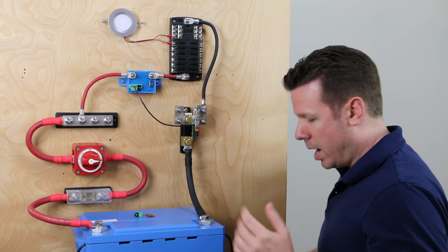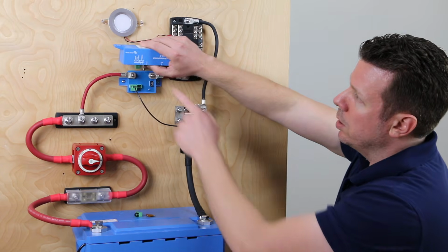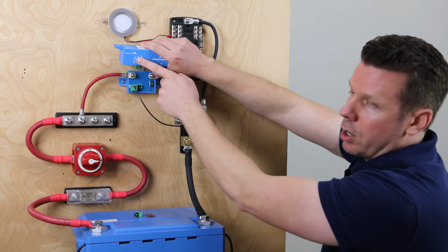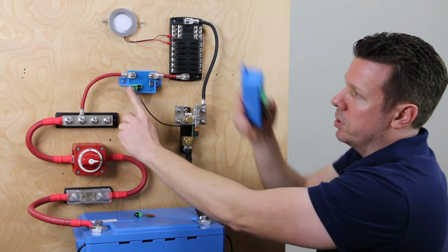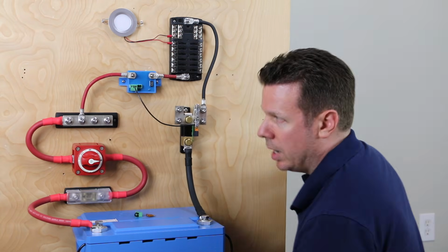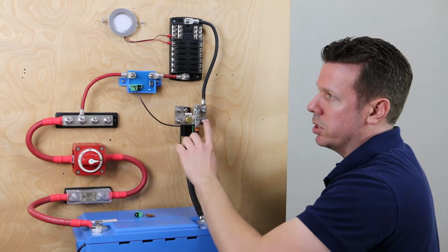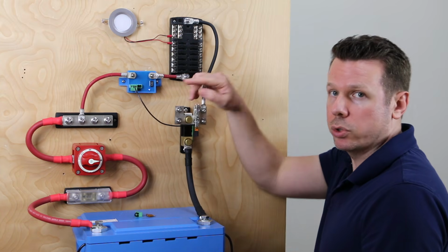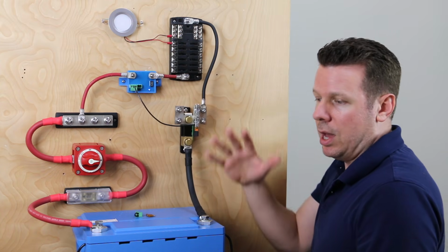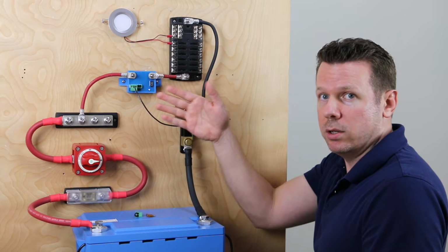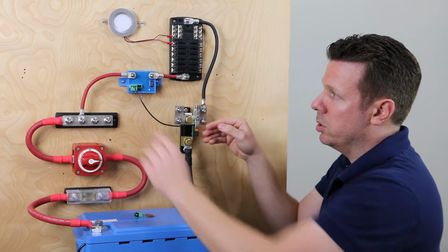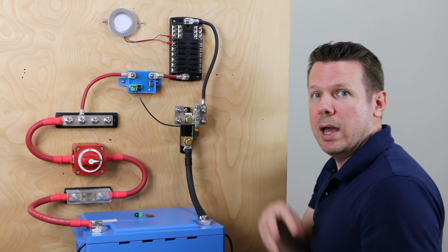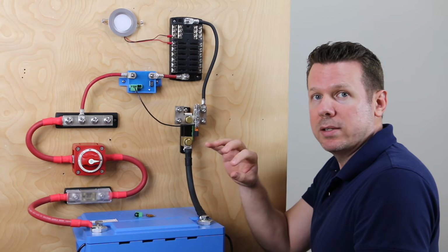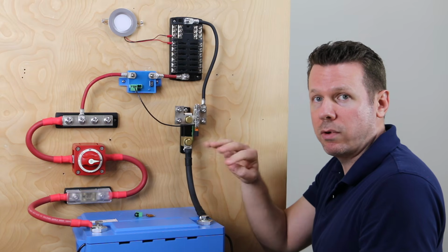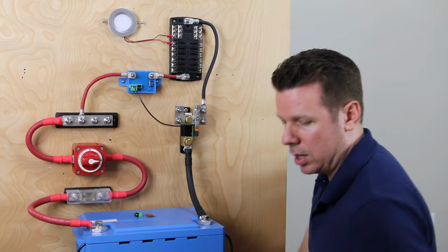There's a terminal called PROG for program, that's the far terminal there. We'll connect that terminal to system negative, and the unit will scroll through its settings. When you get to the setting you like, you pull the wire, disconnect it here or here, and it will stop at that setting and flash to confirm. Let's take a look at that.